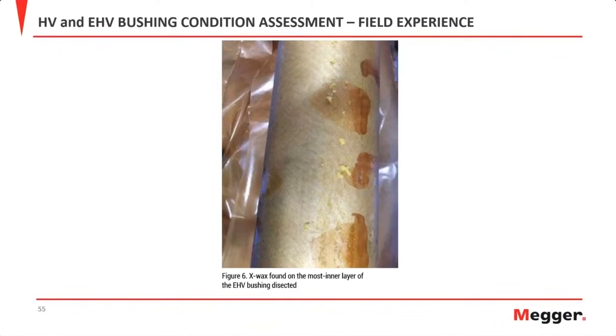We are steadfast in our belief that with more information, you can make better informed decisions. And that's what we're trying to bring here today, talking about looking beyond just the 60 hertz power factor. What else can be found with this individual temperature correction using the Arrhenius equation? What can be found with 1 hertz? And what decisions or conclusions can you make when you look at the full dielectric frequency response of an insulation system?